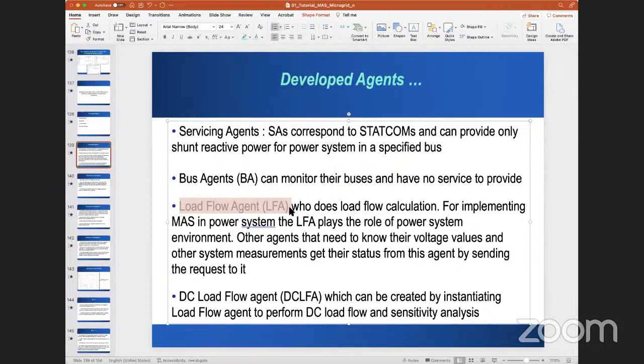They communicate synchronously, so you can do everything on one computer basically. There's a DC load flow agent, which can be created by instantiating a load flow agent to perform DC load flow and sensitivity analysis. Sensitivities, I mentioned many times in the last lecture, are very important. If you understand the Jacobian matrix of the power flow, that's what the sensitivity represents.